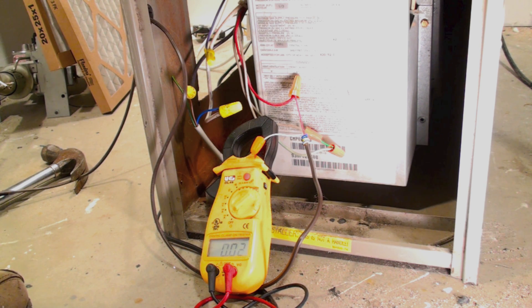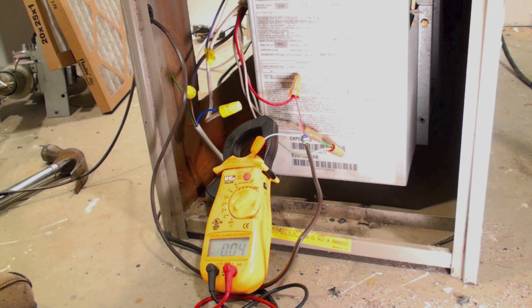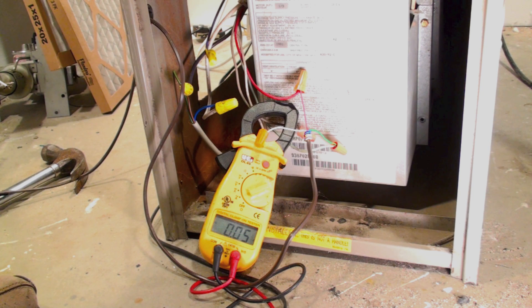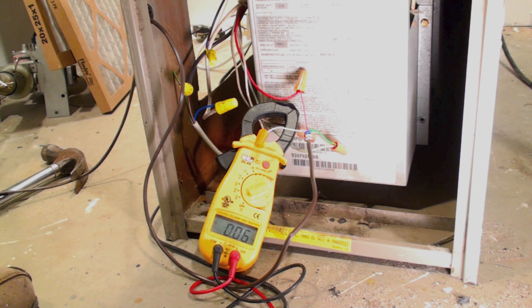Okay, I've got the white clamped and I'm ready to start the appliance. So, I go ahead and turn on the thermostat. Now, that's the inducer. I'm drawing a very low amp rate. I'm 0.06 and 0.07. That's 6 one hundredths of an amp. And that doesn't sound like the right amp draw. So, I'm going to wait until this thing lights off.